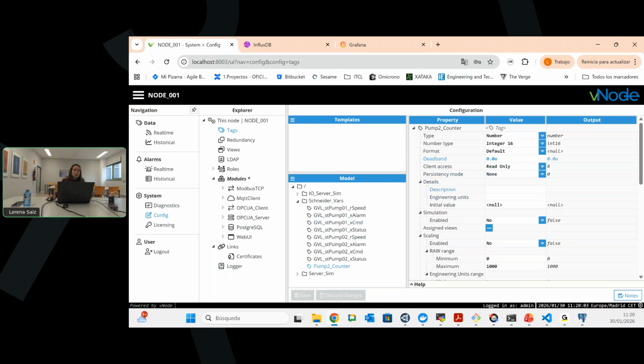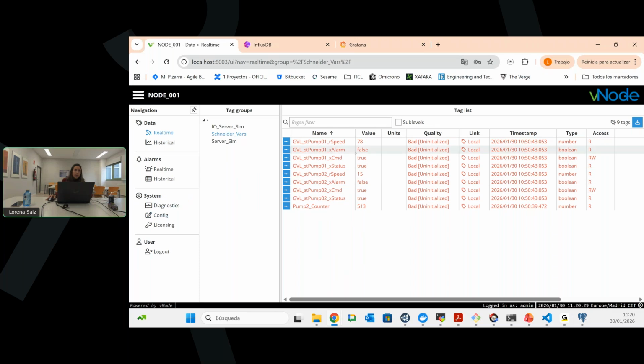And also here, the persistence: just in case the gateway IoT loses connection or stops capturing data, what happens with the last value. I put it as none. Here you could see that the last value is on red, because the last value is not being considered as a correct value. If we record it in memory, probably the connection will still be on, but the timestamp will indicate the last time we collected that data, and we won't get the connection on red.